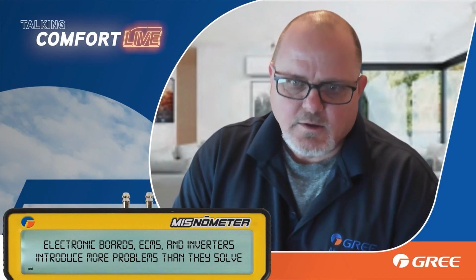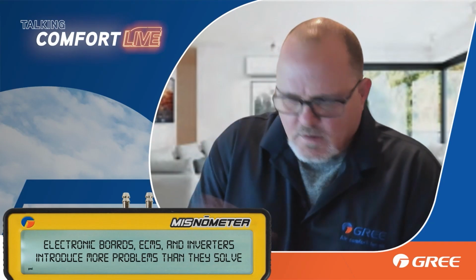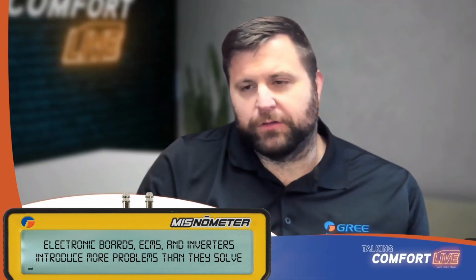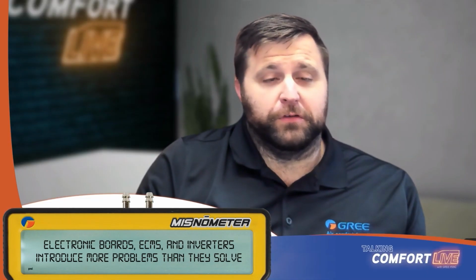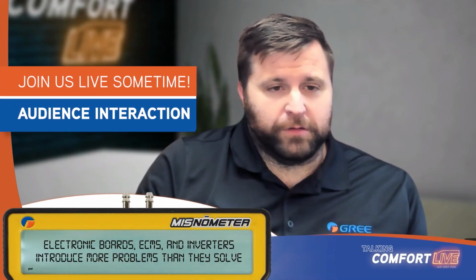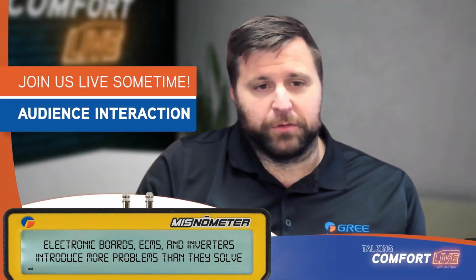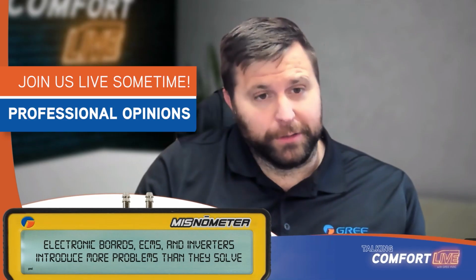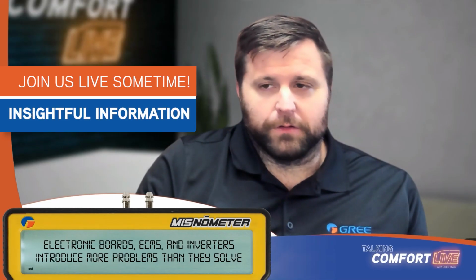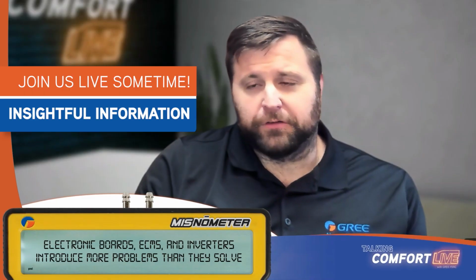It's like having a bad TXV. It's like having a bad sensing bulb, something along those lines. That's what it uses to determine what position it should be in. The EEV is no different in that regard. That's why you have a separate set of thermistors, both inlet and outlet, for each one of those circuits. That's right. And it actually reminds me of another one.